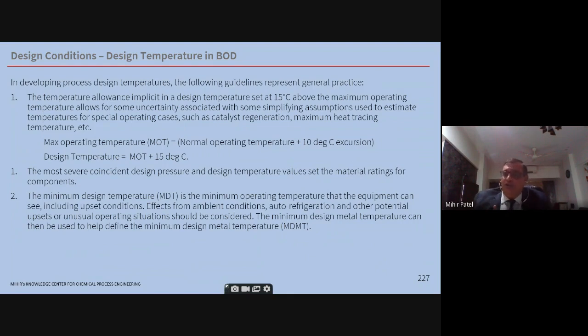Provided there is no other alternative case which can go to a higher temperature. So that 80 degrees is the operating temperature, and 105 is the design temperature. That's how it is. And for the cryogenic liquids, of course, you don't have to add so much. You can keep a minimum margin there for cryogenics.